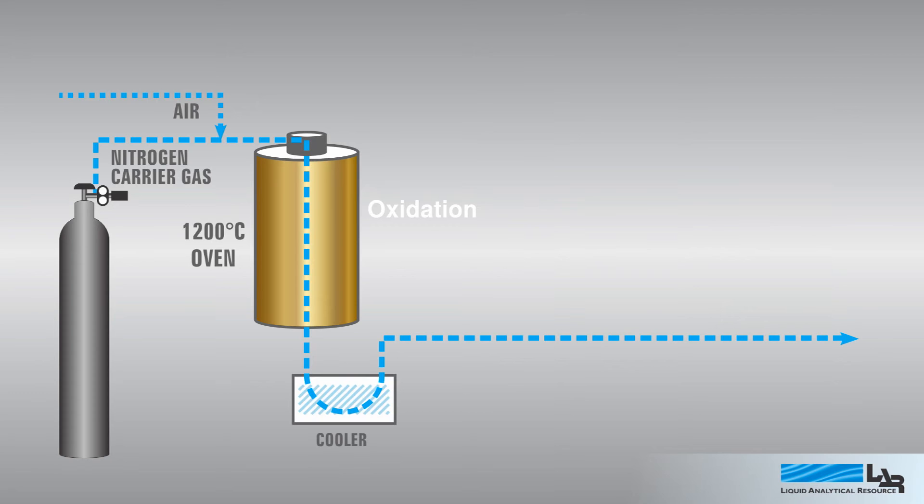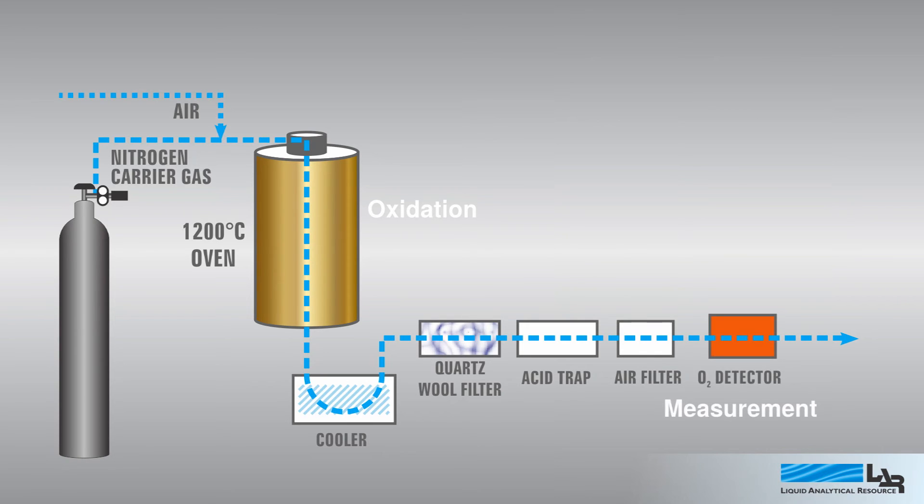The gas is then cooled and sent through a quartz filter, an acid trap, and an air filter. Before exiting the analyzer, the gas passes through a zirconium O2 detector, which continuously measures the O2 level in the gas stream.